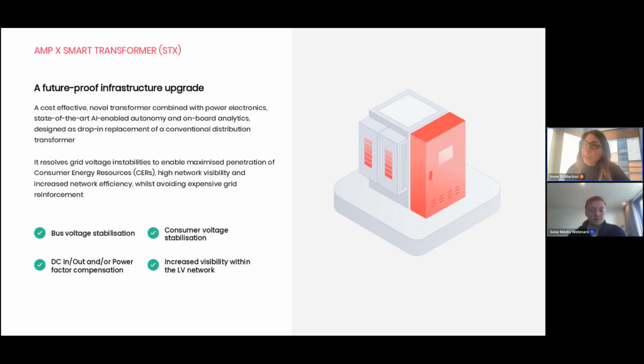The smart transformer is an absolute essential piece of the portfolio of offerings of AMP X, because it addresses the challenges network operators have got in the low voltage network with the emergence of consumer energy resources and the increased pace of decentralization. It's a replacement for conventional transformers. It has an electromagnetic part, but it's also equipped with power electronics and an onboard processor, which allow us to dynamically change the voltage so that it always stays within the statutory limits.